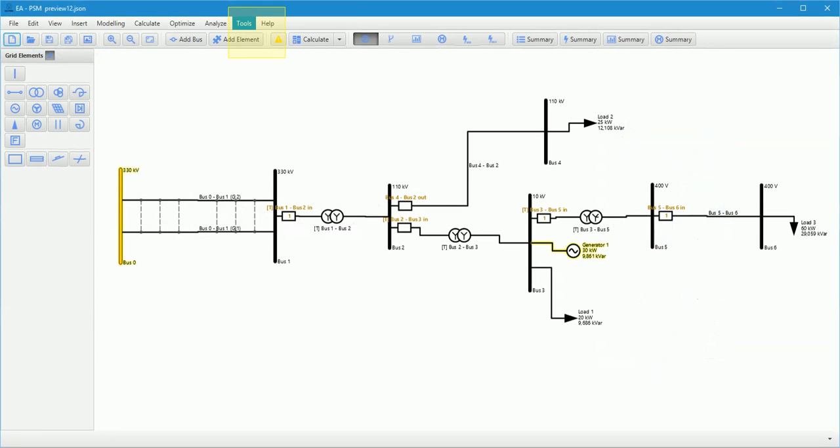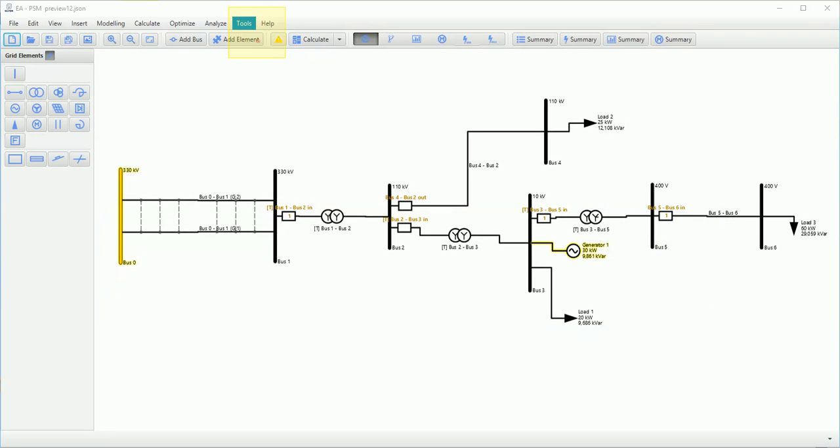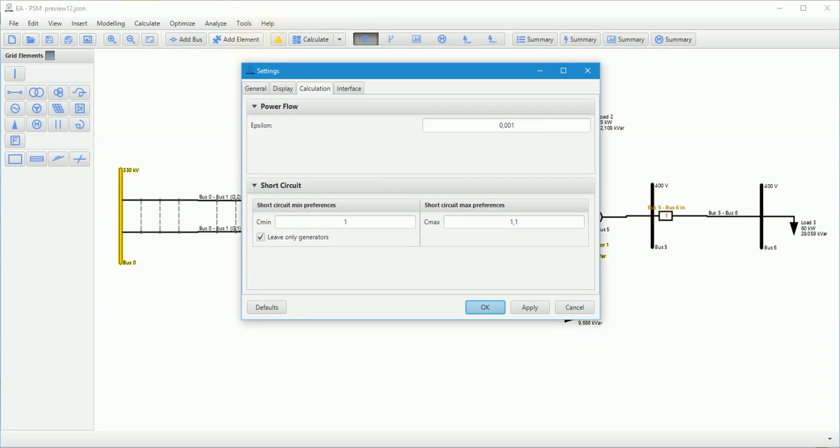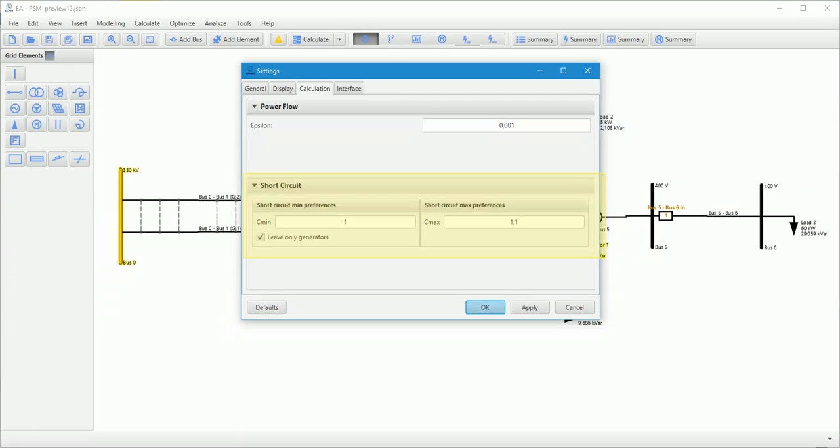User can define C factor in settings. According to IEC standard, the voltage factors Cmin and Cmax are used together with the equivalent voltage source at the short circuit location, in order to calculate minimum and maximum initial short circuit currents.